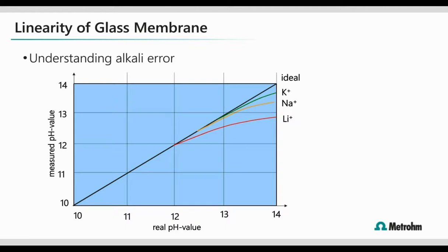Okay. A few slides back, we talked about all of the H+ ion exchange and potential generation that is occurring at the glass bulb or the membrane. As we get into samples of higher pH values, we run into what is called the alkali error range. In strongly alkaline solutions, a standard electrode may give measurement errors due to the potential contribution of other alkali ions, so think potassium, sodium, lithium. When we get into these higher pH values, there are so few H+ ions in the solution that not only does the pH get difficult to measure, but we've got those other +1 ions contributing. So rather than an ideal straight linear relationship across the pH measuring range, pH values can appear to be lower.